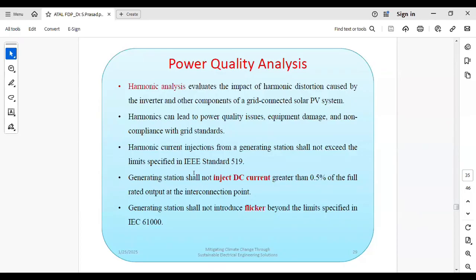And DC current also should not be more than 0.5% of the full rated output at the interconnection point. It should not be more than 0.5% at the point of interconnection. That you have to take care. Similarly, flicker: generating stations shall not introduce flicker beyond the limits specified in IEC 61000. So these are the standards we are following: IEEE standard 519 for harmonic analysis, IEC 61000 for flicker analysis.